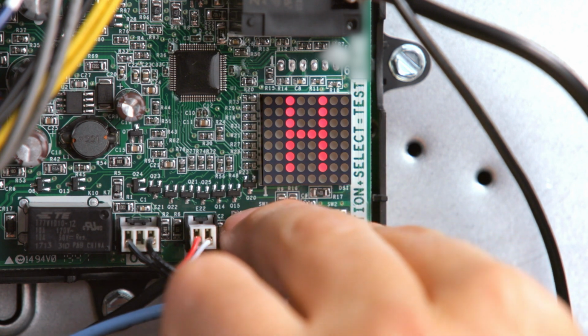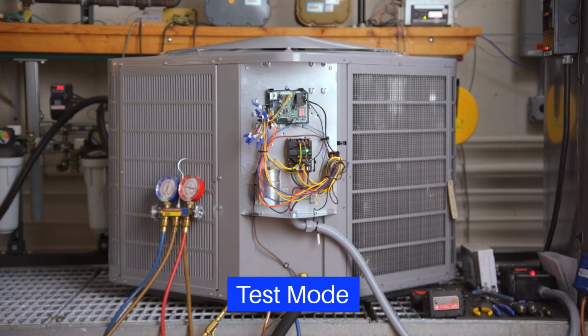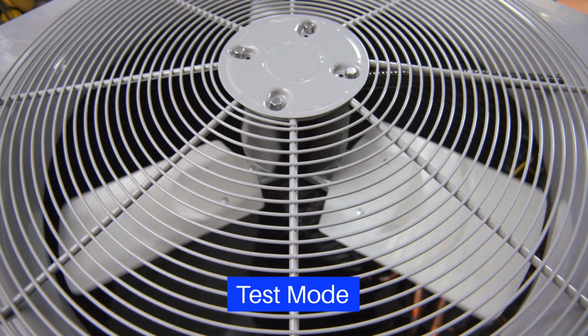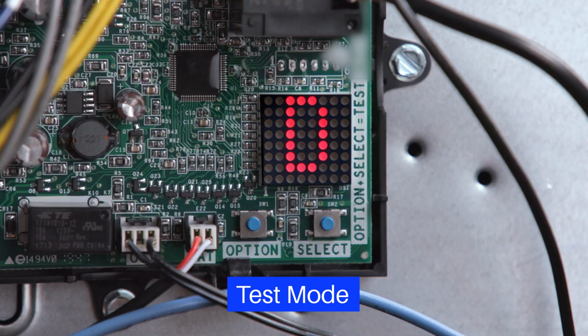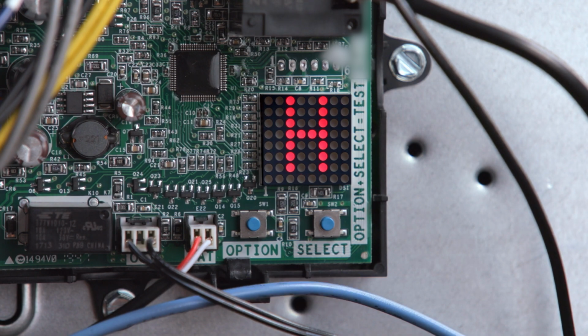Press Option and Select for 1 second, and the control will display a T for test mode, followed by a D for defrost. During test mode, the reversing valve will change direction. The auxiliary heat will energize, the outdoor fan will turn off, the defrost test will end, and the control will once again show an H. The control is now ready for operation.